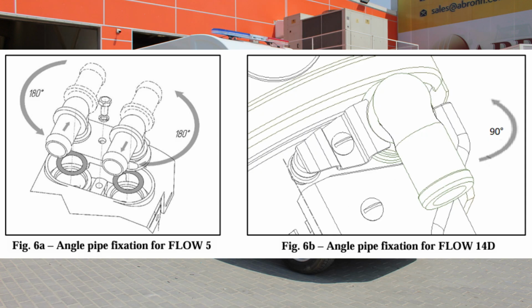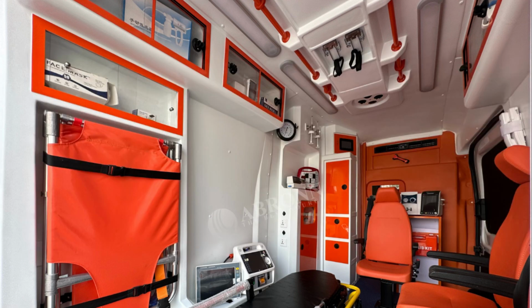Angle pipes. To assist the installation process, the angle pipes can be turned by 180 degrees for flow 5 or by 90 degrees for flow 14D as shown in Figure 6A and B. To turn the pipes, loosen the screw in the fixation plates. Turn the pipes to the desired position and retighten the screw in the fixation plate. Do not rotate the pipes while the screw is being tightened. It will damage the gaskets and cause a leak. Angle pipes can be changed for straight pipes in the flow 5. These pipes are sold separately.